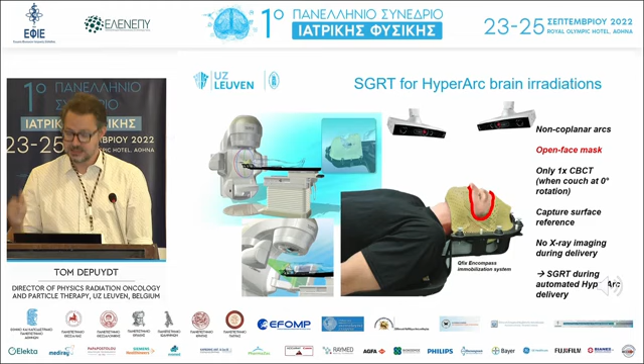And that's in the version that we have right now. It's fully automatic. So there's an integration between the TrueBeam and the Vision RT alignRT software that transfers the expected angle. And in this way, it can be monitored and verified that the patient is in the right position without any X-ray imaging. Now you see there are some spikes, but that's due to the fact that the synchronization is not optimal, so it can expect another angle, but at some point it knows, and it only lasts a few milliseconds. So that's what we do in conventional linear accelerators with SGRT.